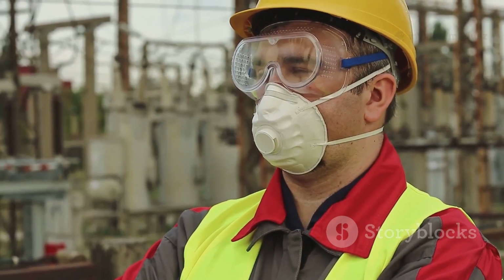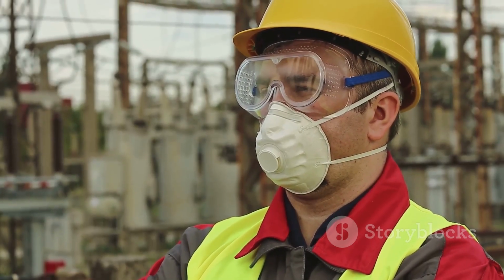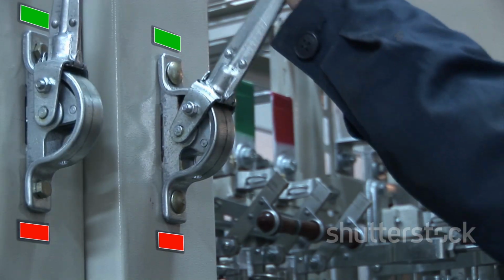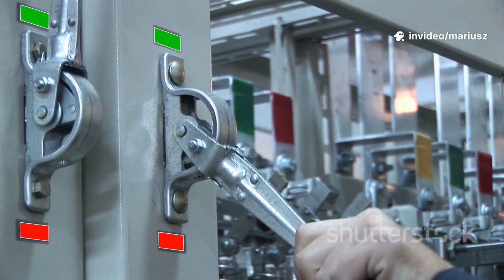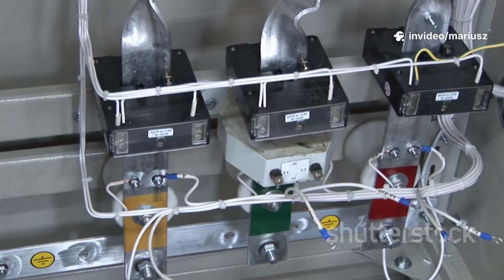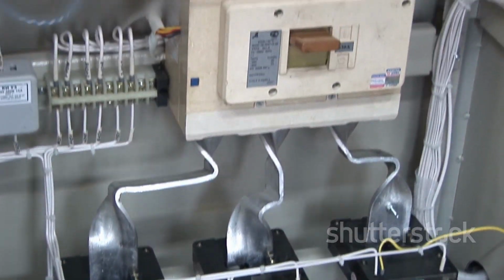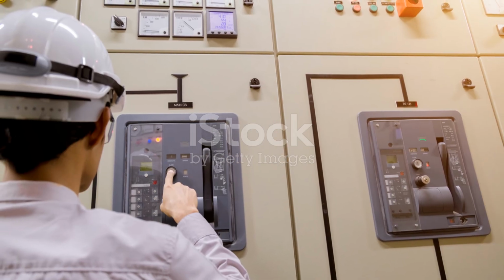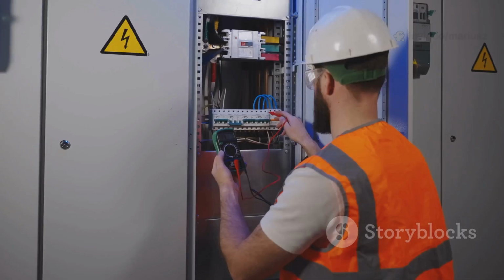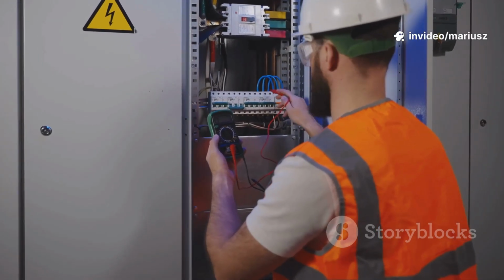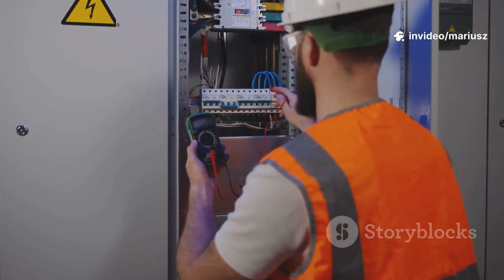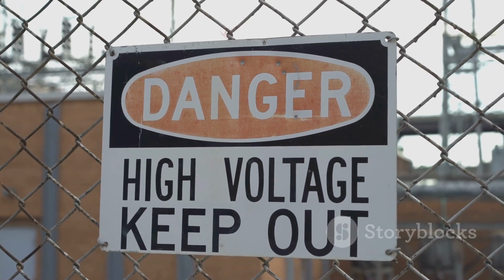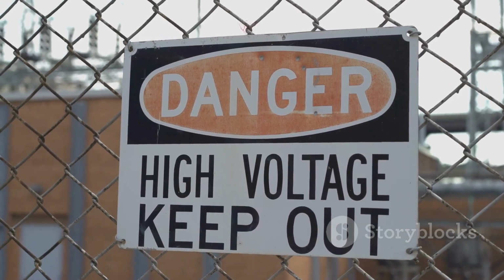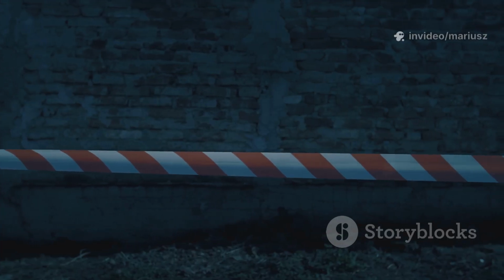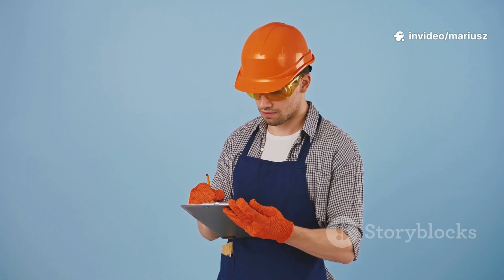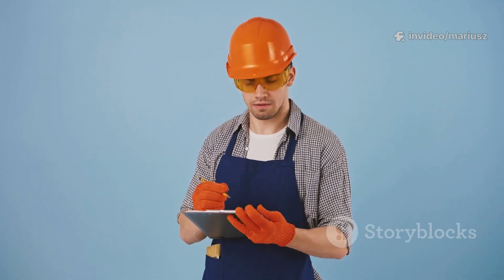Once the plant is correctly identified, the second stage is isolation. The authorized person goes to the relevant switchgear or valve stations and disconnects the equipment from all sources of energy. As we've discussed, this means racking out circuit breakers for electrical systems or closing and locking specific valves for mechanical systems. Every isolation point is secured with a safety padlock, to which only the authorized person has the key. A caution notice is then attached at these isolation points, warning others not to interfere with them. This creates a secure boundary that cannot be breached accidentally. It's a deliberate and documented action that forms the first layer of physical protection.